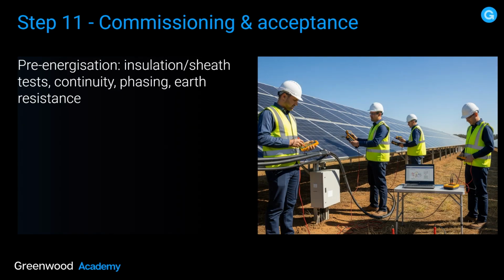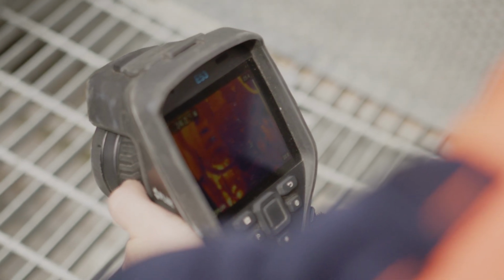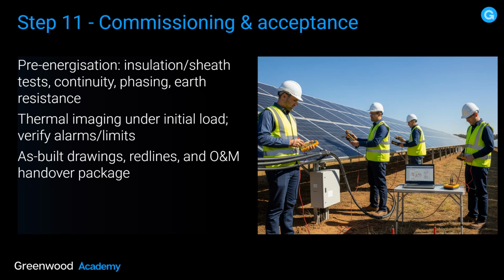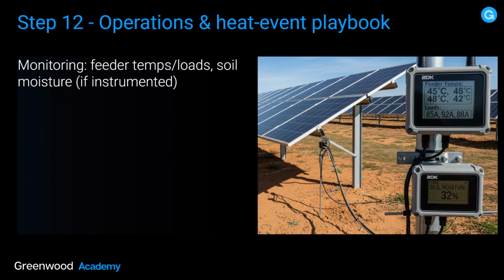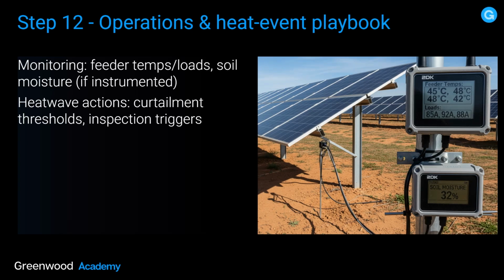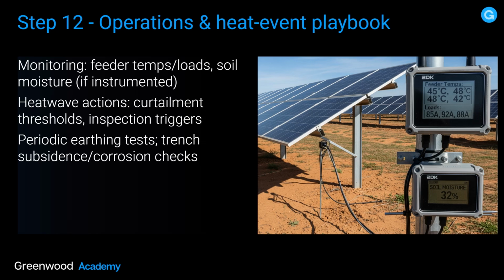Step 11, commissioning and acceptance. Pre-energisation, insulation, sheath tests, continuity, phasing, earth resistance. Thermal imaging under initial load, verify alarms and limits. As-built drawings, red lines, O&M handover package. Step 12, operations and heat event playbook. So you're talking about monitoring feeder temps, loads, soil moisture if instrumented. Heat wave actions, curtailment thresholds, inspection triggers, periodic earthing tests, trench subsidence and corrosion checks.